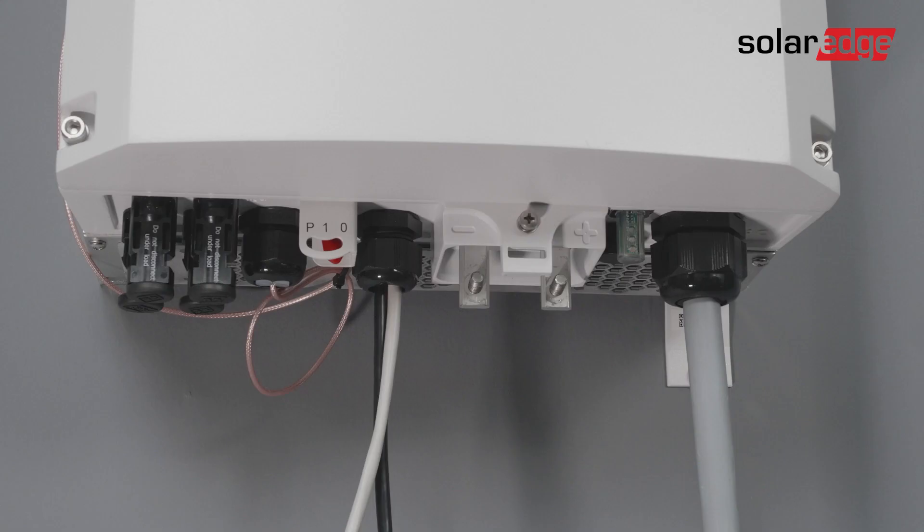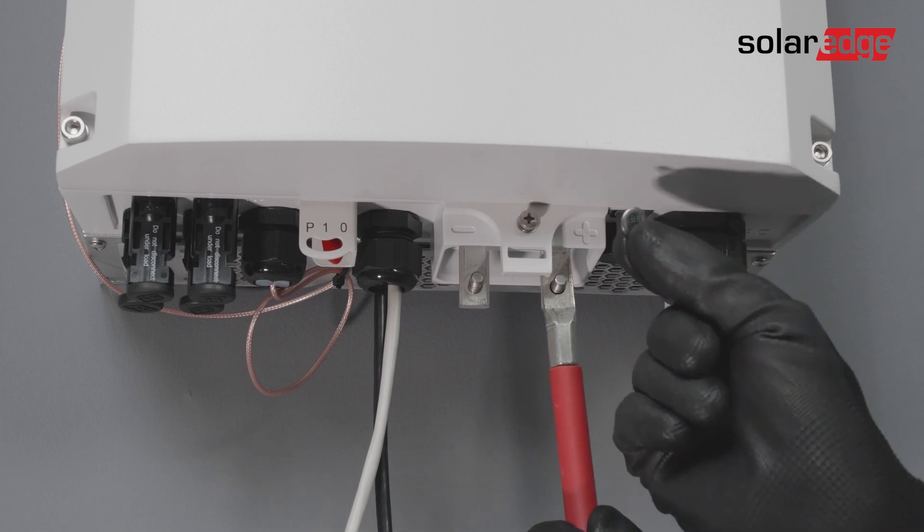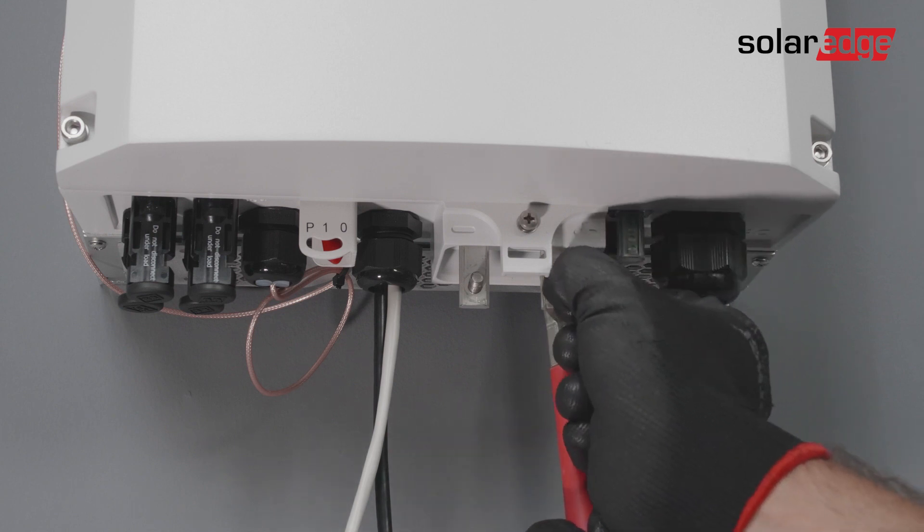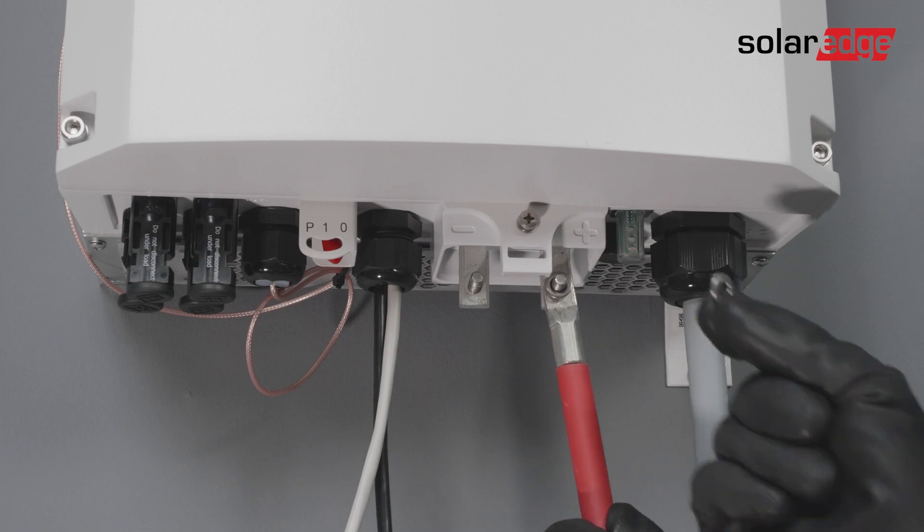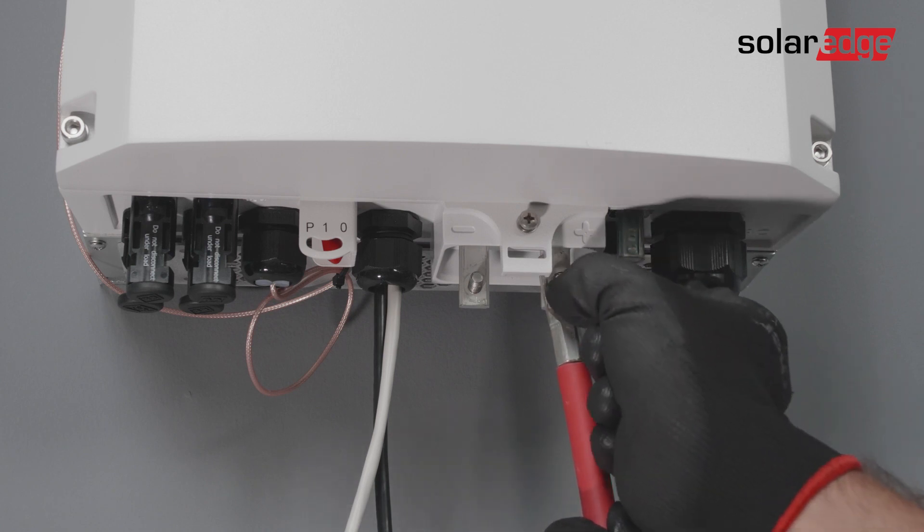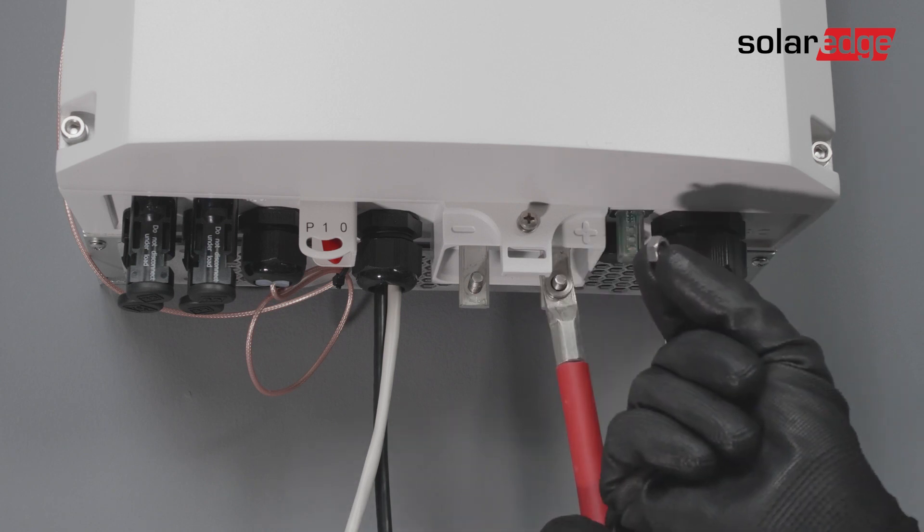Now, connect the DC cables with the supplied screws. Please note the polarity as noted also on the inverter. The correct assembly order of the washers is to first assemble the flat washer, then the spring, and finally place the bolt.